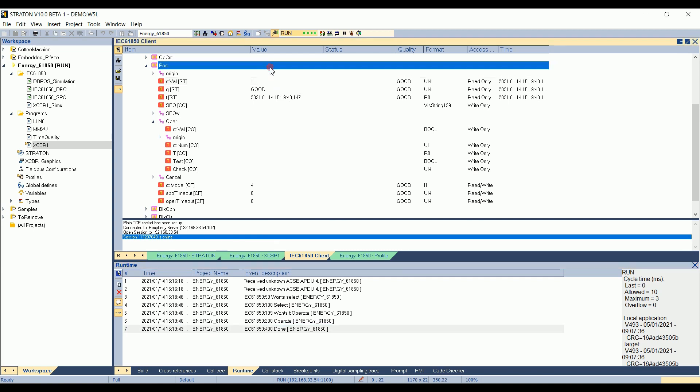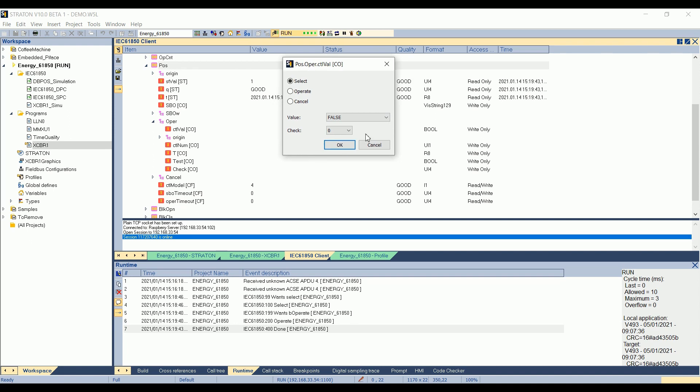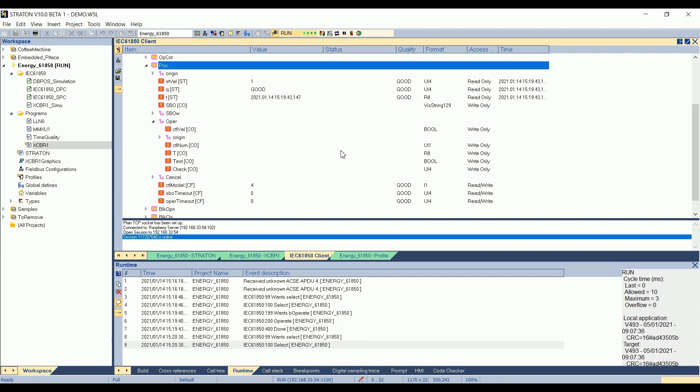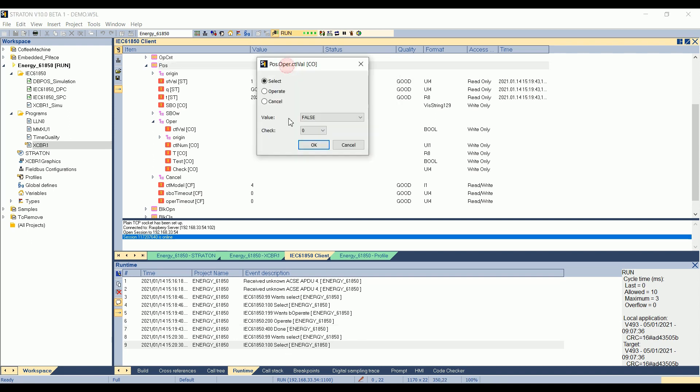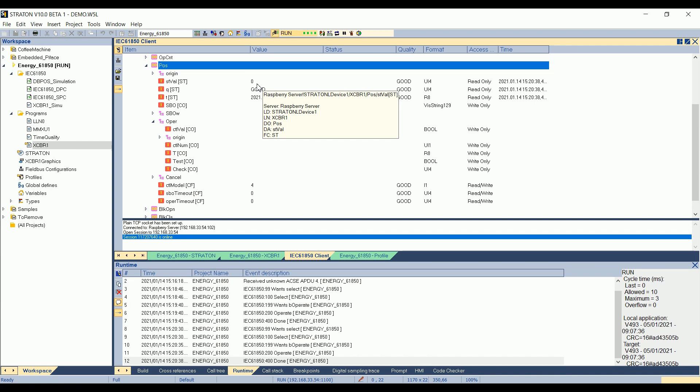If you want to set the position to false, we send a select to false. So, circuit breaker position to off. OK. The select is sent. Then we send the operate to false. The value is changing to 2. Intermediate state. And then to 0.